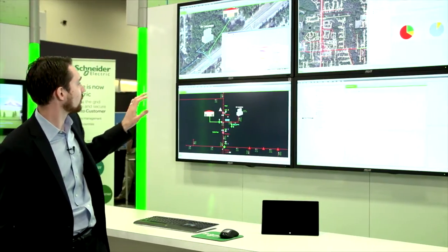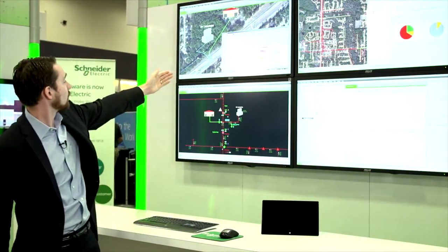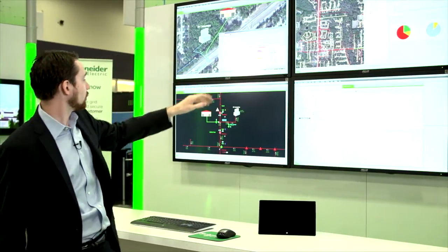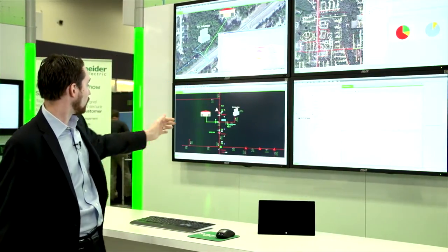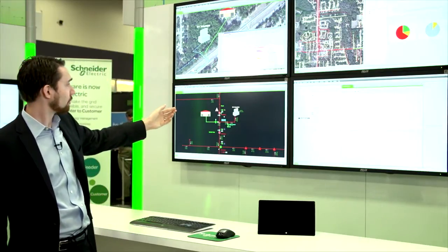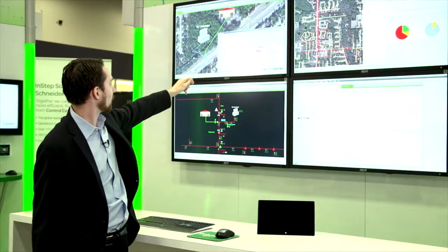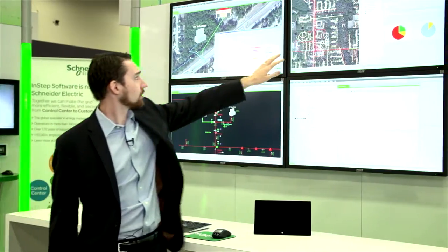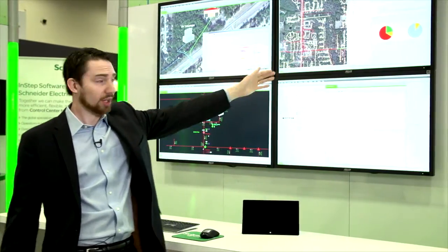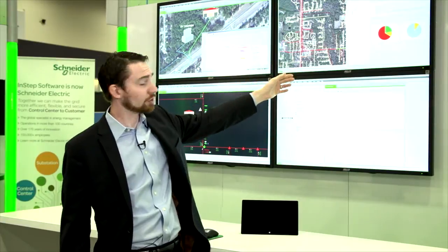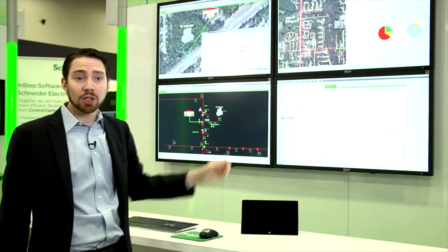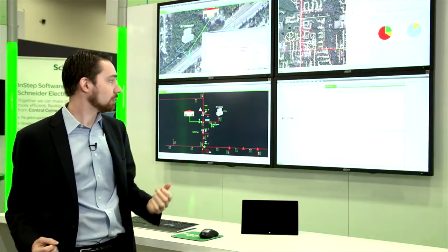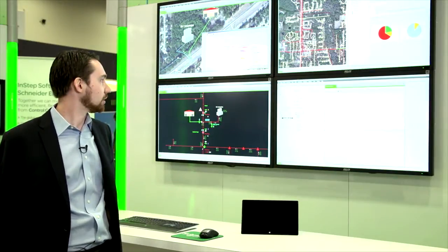Some of the other functions we have here — if you look at the upper left screen, we have our voltage profile. For any line we click on in the system, we can get load flow information, state estimation information, and a voltage diagram that shows what the voltage is across your entire feeder. We also have other diagrams and dashboards we can quickly pull up. For instance, this is state estimation data right here, which compares your SCADA information with your load flow modeling to give you an accurate picture of what your data looks like.